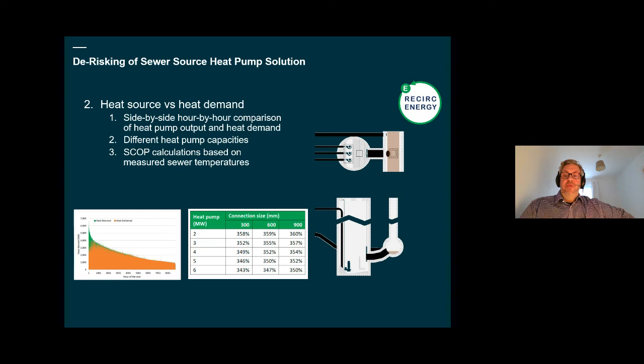We took those flows and did a conceptual sewer connection design, sketched out on the right, and used that to calculate the amount of water we could abstract from the sewer given different connection designs and sizes, then used that data to model what size of heat pumps we could have. There's a table showing heat pump size down the left and connection size at the top.